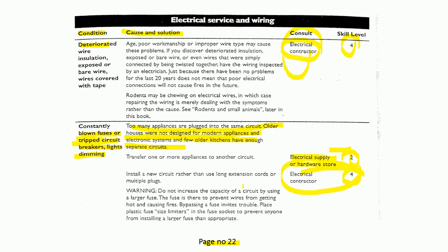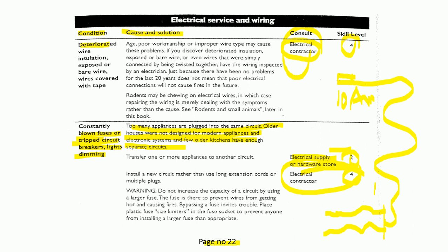So here, let me explain this one. 10 years ago, 50 years ago, somebody put here a fuse which says this is 10 amp. Now I have a wire connecting, and then I have this outlet, with two outlets here. Maybe I will run them sometimes simultaneously. So I have something here 5 ampere, and something 4 ampere or even 6 ampere. If you run both simultaneously, it will be overheated. This wire has been designed for 10, now it's 11, maybe okay, a little bit overheated.